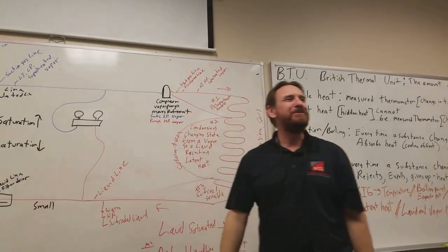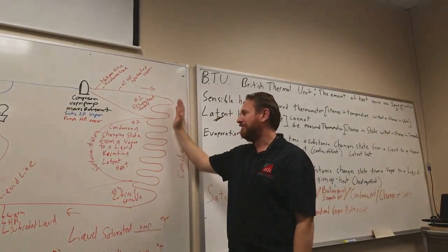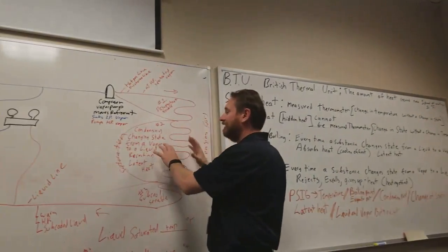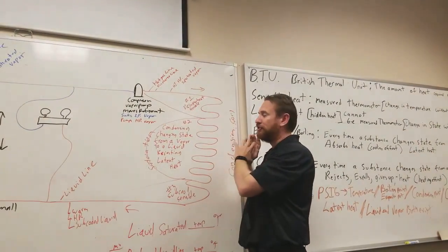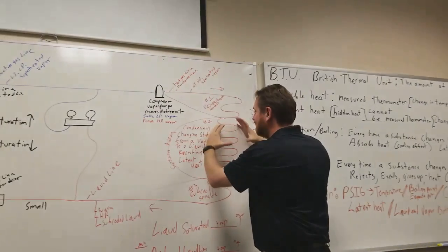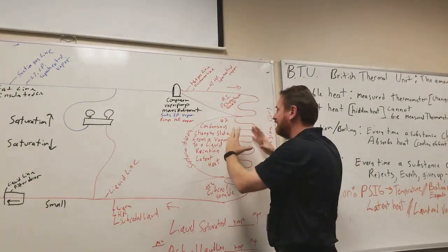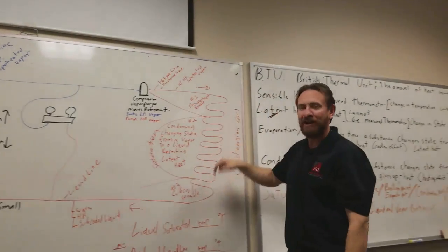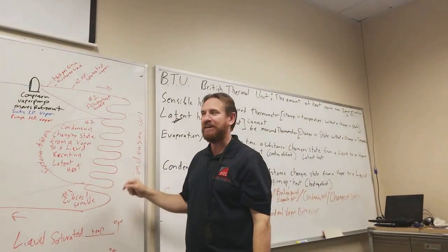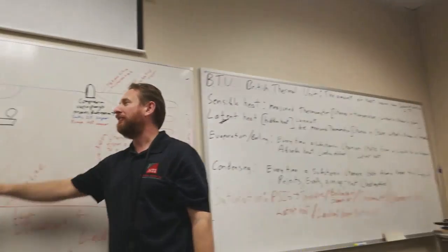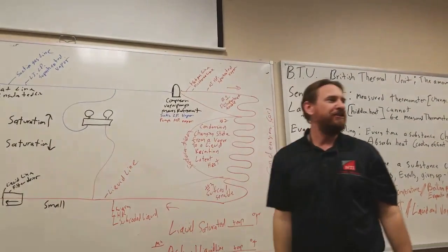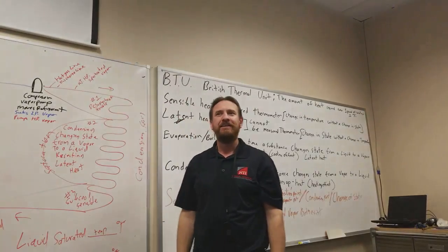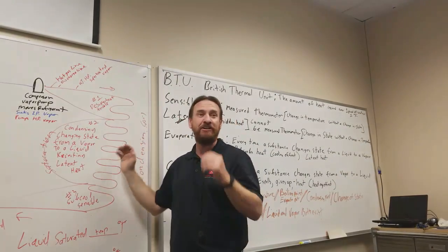Your saturation temperature. So yesterday, when we blocked that with plastic, it was causing less air transfer. It was changing the heat transfer. The heat staying here instead of being pushed away by the fan. Now we have more temperature right here, which means more pressure inside. More pressure inside means the pressure goes up. And the pressure goes up, the saturation temperature also goes up. Does that make sense? Yes. That's what was happening yesterday when we were changing that and adjusting that.